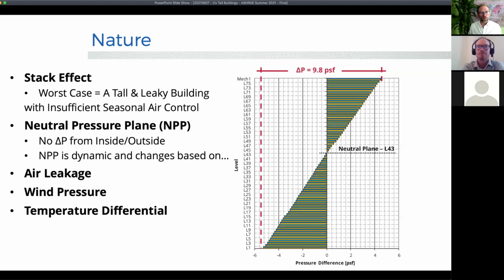When we're in a northern climate working on a high-rise multifamily residential building, we like to confirm the stack effect calculation wherever possible. We'll do the temperature calculation, and we have the benefit in multifamily buildings of operable windows on every floor—that can be a benefit and a deficit, depending on how you look at it. We'll send our team through to open a window and see if the air is going in or coming out, and we can find the neutral plane pretty quickly, seeing how far above or below we are.